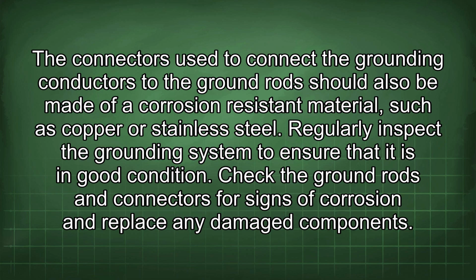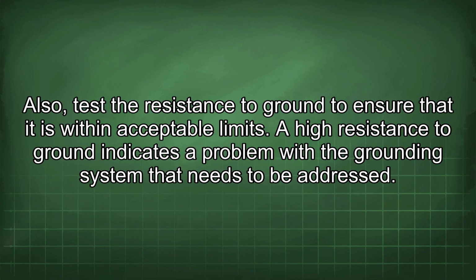Regularly inspect the grounding system to ensure that it is in good condition. Check the ground rods and connectors for signs of corrosion and replace any damaged components. Also, test the resistance to ground to ensure that it is within acceptable limits. A high resistance to ground indicates a problem with the grounding system that needs to be addressed.